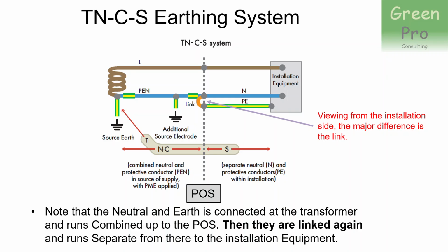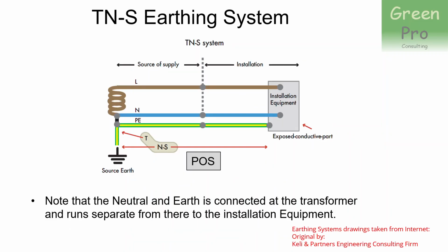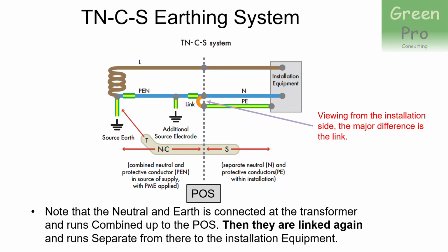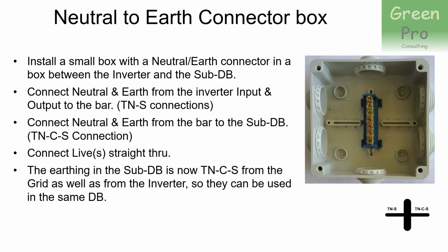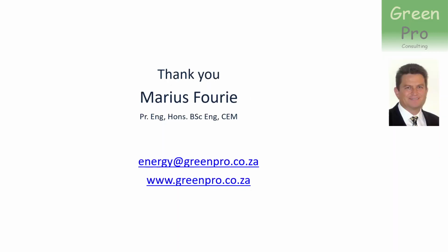So this is where you put that link in the TNS system, and you make it a TNCS system, and that link is in fact that bar. The live in all cases simply goes straight through, and the earthing in the DB is now a TNCS system, both from the grid as well as from the inverter, so they can be used in the same DB.